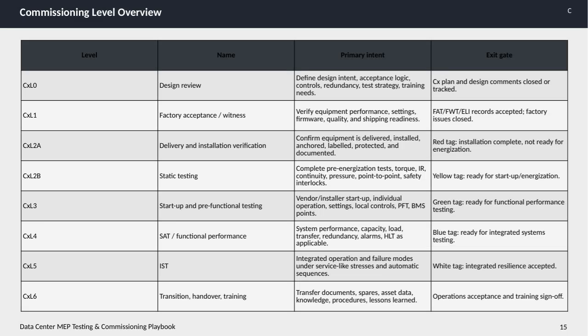Here we have an overview of the commissioning levels important for data center MEP testing and commissioning. The process is structured into several stages, each with a clear purpose and exit criteria to ensure quality and readiness. Starting with CxL0, the design review defines the design intent, acceptance logic controls, redundancy, test strategies, and training needs. This step closes or tracks all design comments and finalizes the commissioning plan. Next is CxL1, factory acceptance and witness testing. This stage verifies equipment performance, settings, firmware, quality, and shipping readiness. Only after reviewing and accepting factory test records and resolving any issues can we proceed.